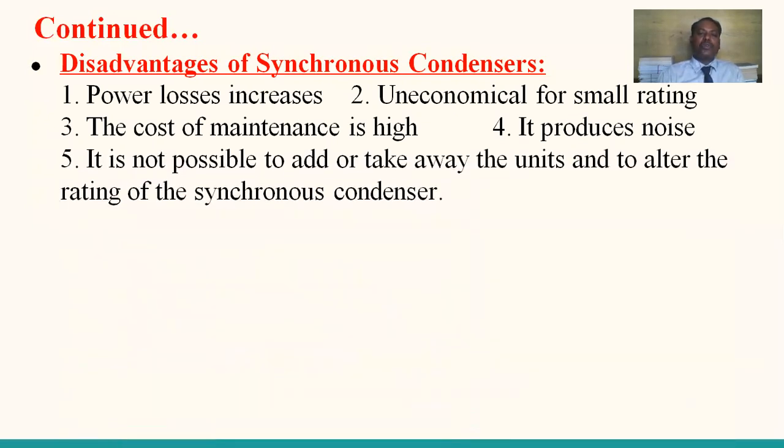And it is not possible to add or take away units to alter the rating of a synchronous condenser, unlike static capacitors, which have the facility to add or remove units. In the case of synchronous condensers, there is no possibility to add or remove rating because it is a fixed rating of the motor. Whatever the rating of the motor, based on that, the kVAR requirement, either injected or absorbed, is possible. Apart from that, it is not possible to add or take away kVAR units.